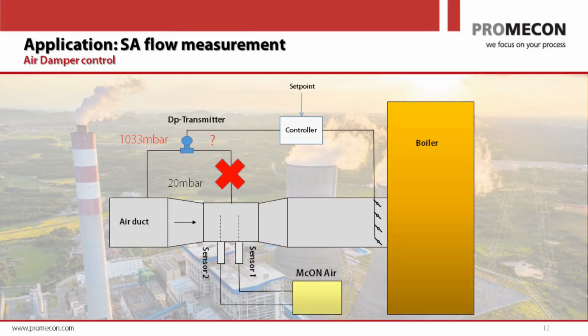Your operator usually can't see these effects because your dP transmitter is hooked up to a controller, to a DCS system. And the DCS system is controlling your louver dampers. And it controls the louver dampers so that the flow that goes into your boiler reaches the set point again, right? So in your DCS, you have a certain set point, let's say so many pounds per minute of air. And if your delta P transmitter is drifting, let's say it's drifting down, then the louver damper opens up. And it opens up so long until the measurement value of the DP transmitter reaches the set point again. That's what some people call a self-fulfilling prophecy, right? The controller basically forces the louver damper into a position where the DP transmitter shows the value that the DCS system is expecting. So your operator sits in front of the screen.